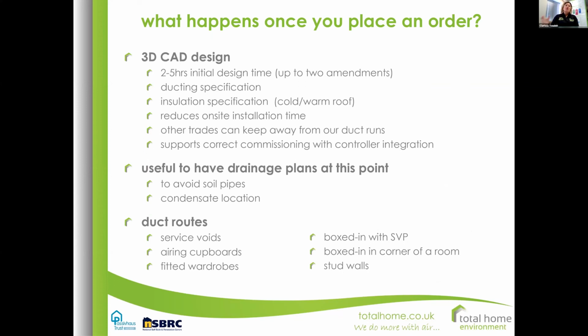Once you place an order, you should get a 3D CAD design done, which gives exact ducting specification, and shows where the duct's having to run through a cold space, for instance, and needs more insulation. This really does reduce on-site installation time, and it helps other trades keep out of the way of these ducts. These ducts are quite large, and they're not very flexible in where they can go in comparison to the tiny bore copper pipe that, for instance, your plumber will be putting in.